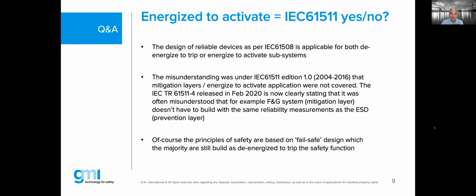So again, design of reliable devices, such as in fire and gas applications, we need to look at the reliability of those devices also. And I'll give you a classical, common mistake. I'm not pointing a finger at any vendor in the market at all, it's just a general, neutral example. Assume that you have a gas detector, and the gas detector has the reliability quality of SIL2. It is SIL2 suitable. It has a systematic capability of SC2. There are even some SC3 on the market.